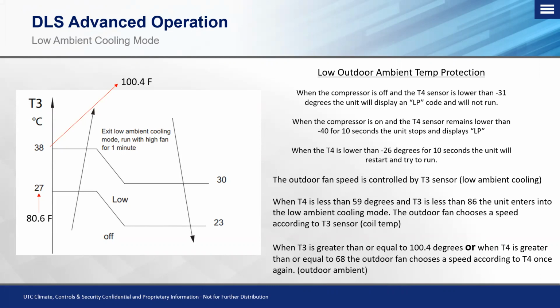Again, by default, the outdoor fan speed is controlled by the outdoor ambient temperature sensor. During a low ambient cooling operation, it switches away from that T4 or outdoor ambient sensor and now controls it based off of outdoor coil temperature, which essentially acts like a motor master on your rooftop style unit, or a motor master if we're looking for low ambient cooling operation for server room units.